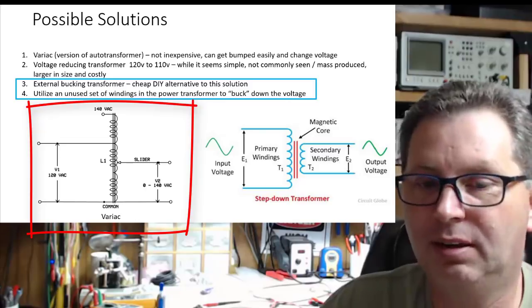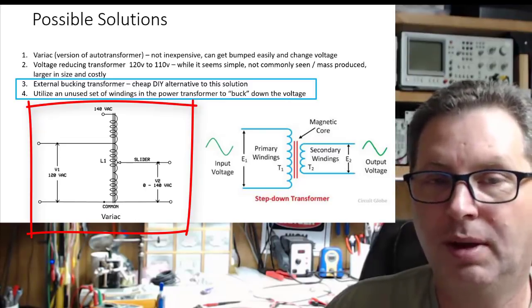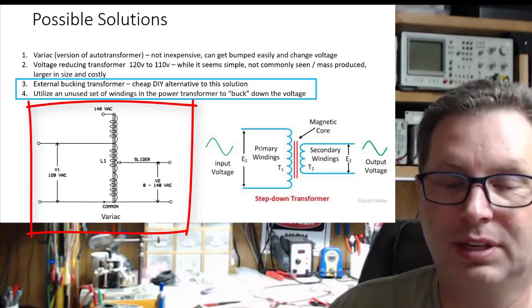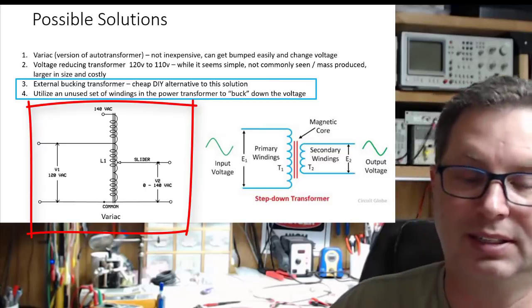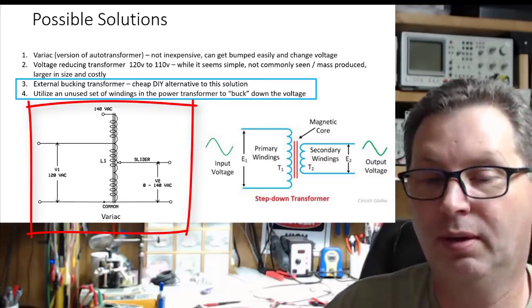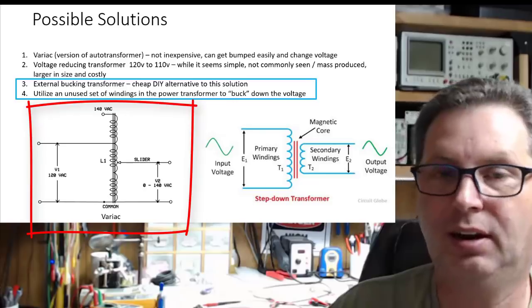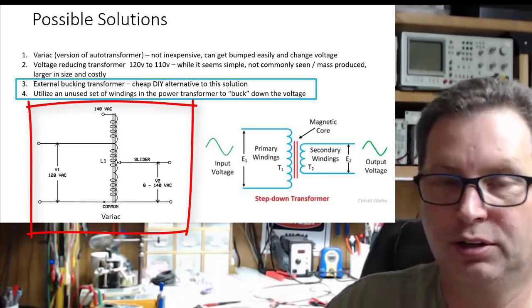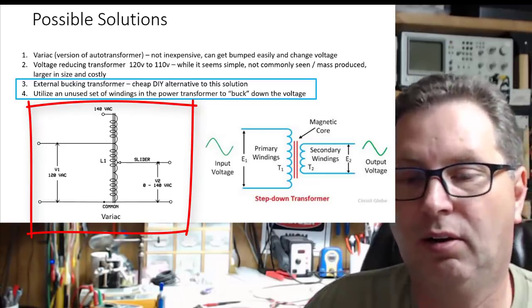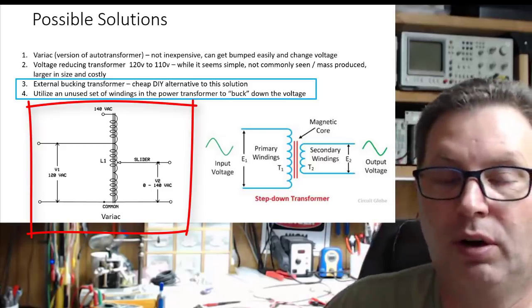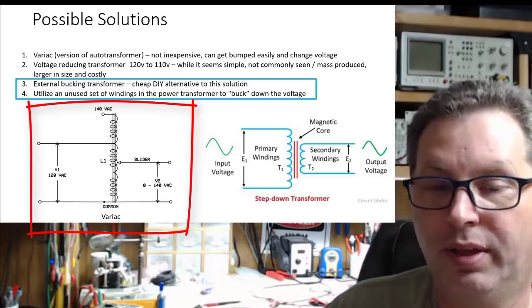So if you have a fixed input of 120 volts, you may on the output get all the way down from 0 volts. Sometimes these things even have windings that let you put out more on the secondary than on the primary, meaning you've added more turns to the secondary. So you may be able to adjust from 0 to 140 volts on the output.